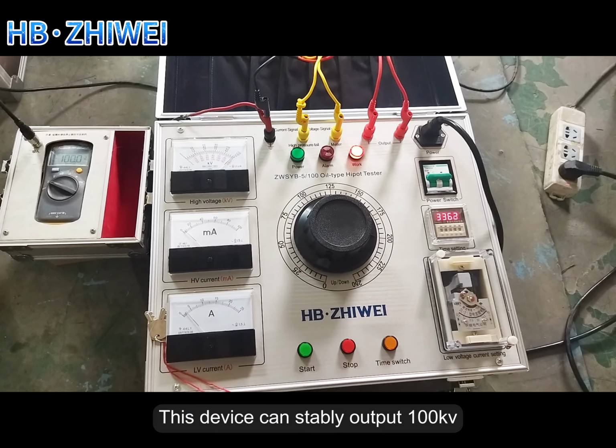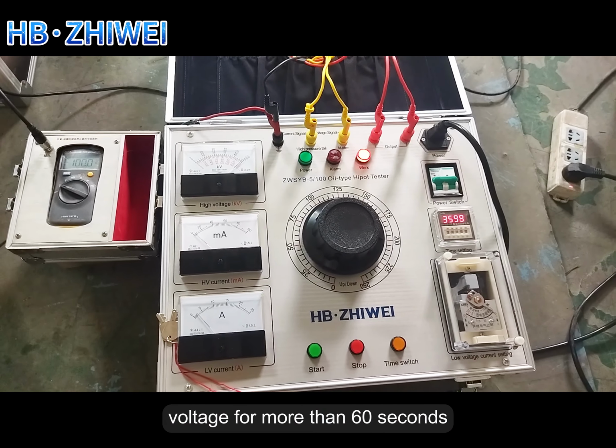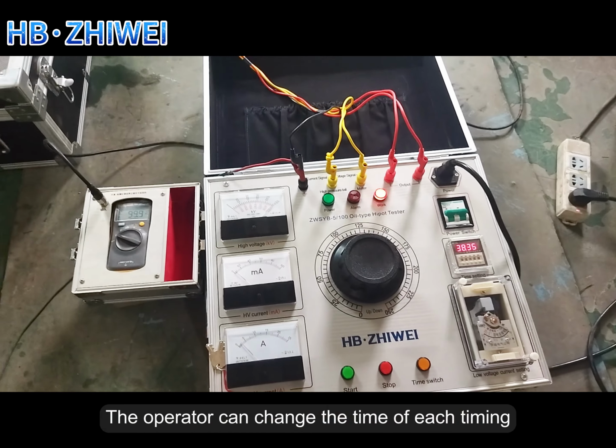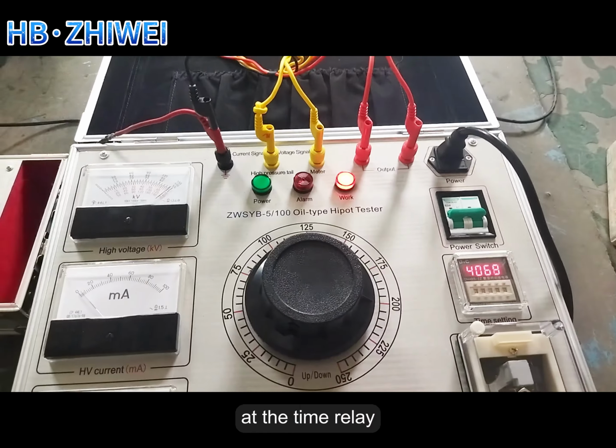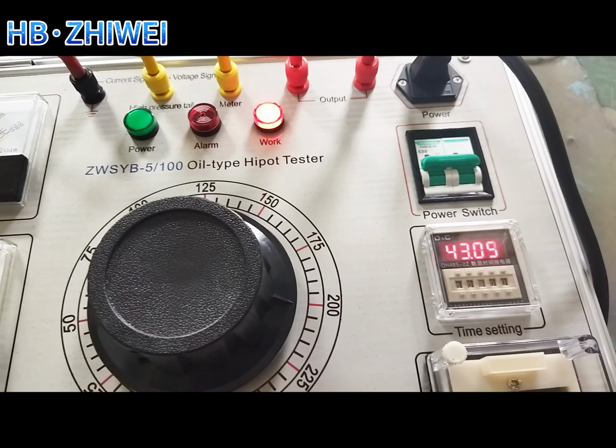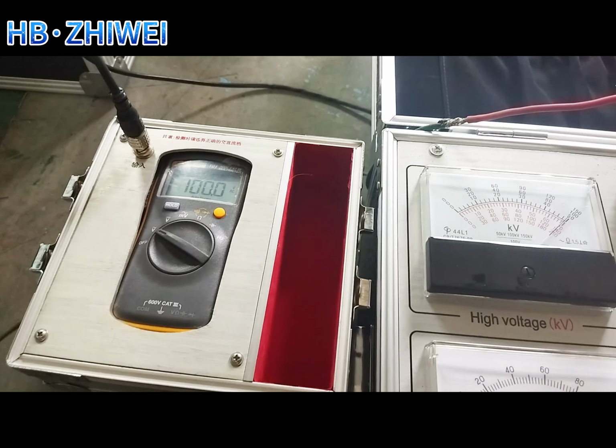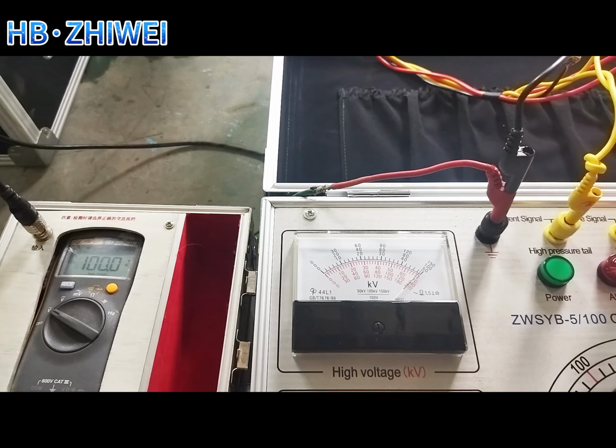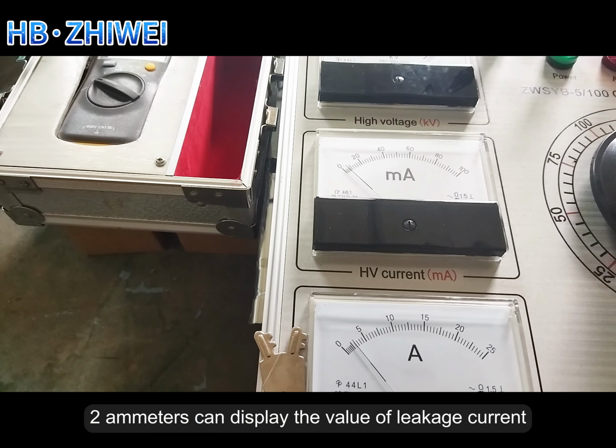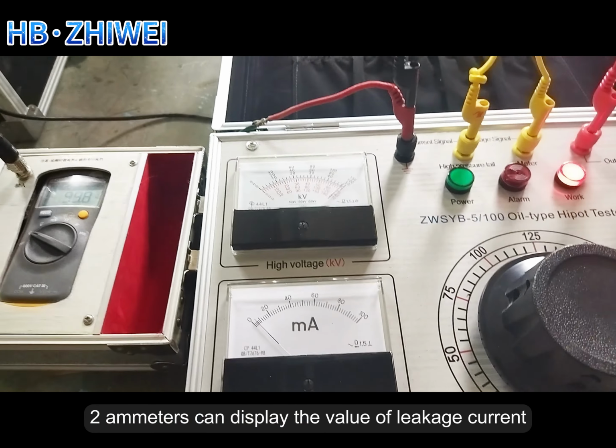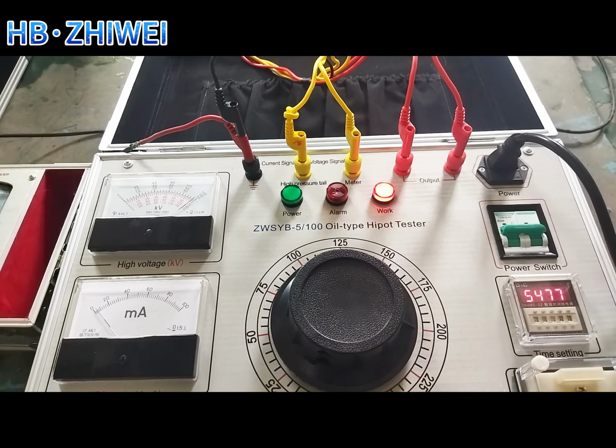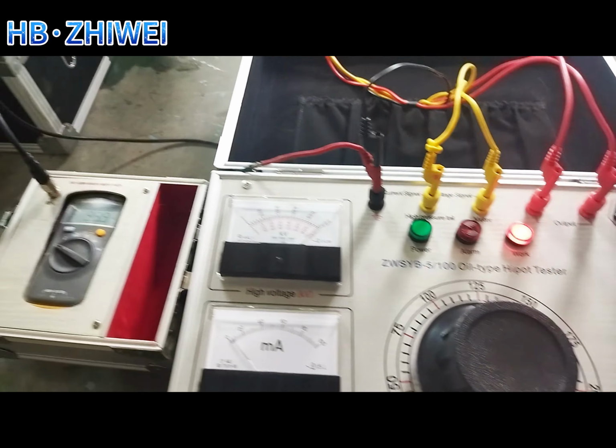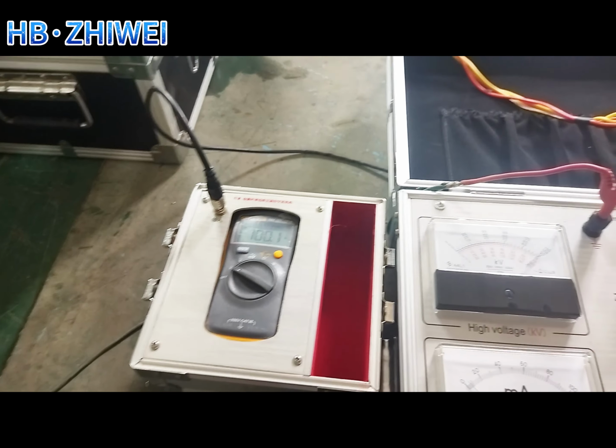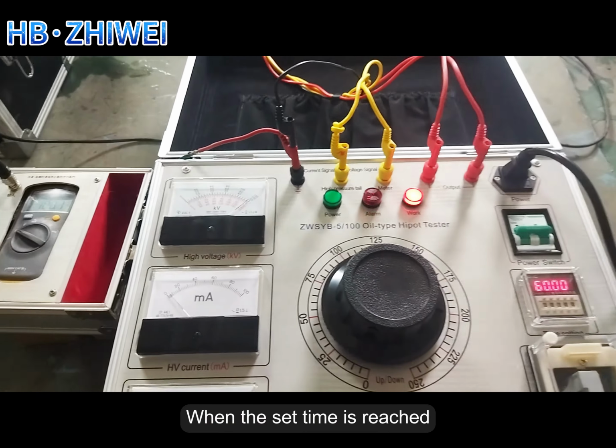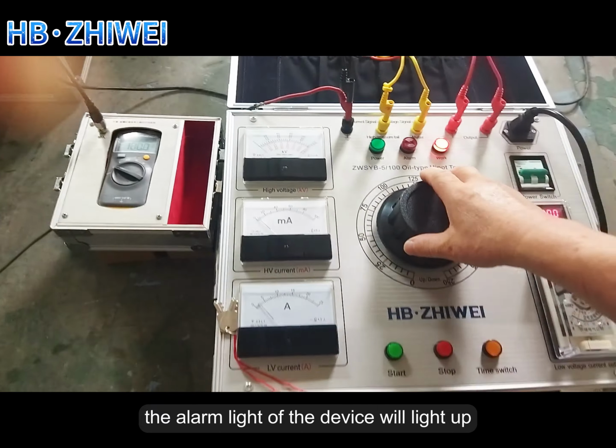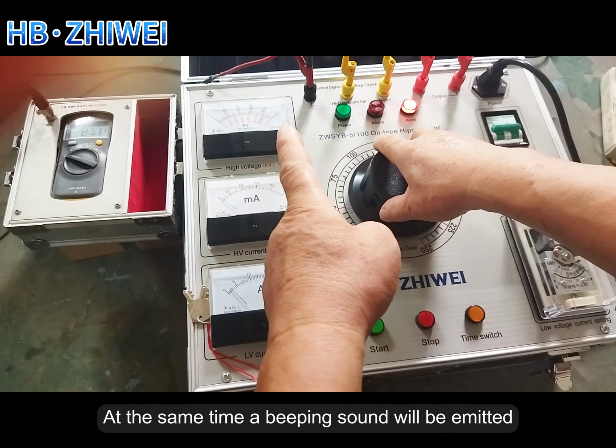This device can stably output 100 kV voltage for more than 60 seconds. The operator can change the time of each timing at the time relay. Two ammeters can display the value of leakage current. When the set time is reached, the alarm light of the device will light up. At the same time, a beeping sound will be emitted.